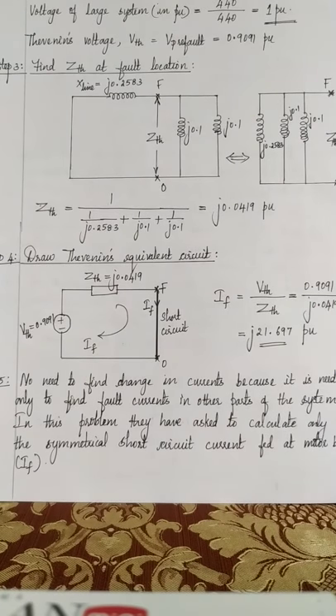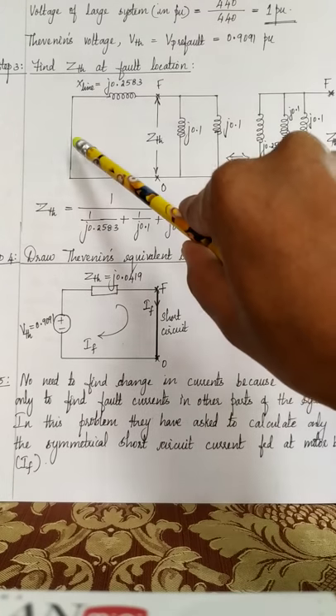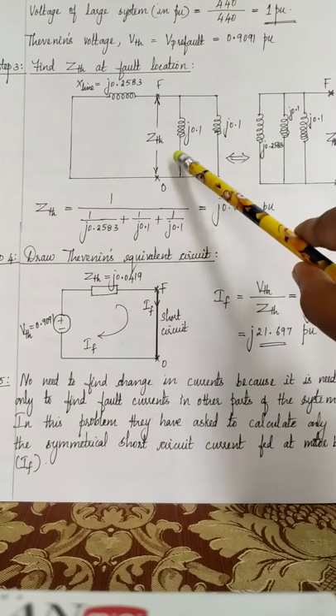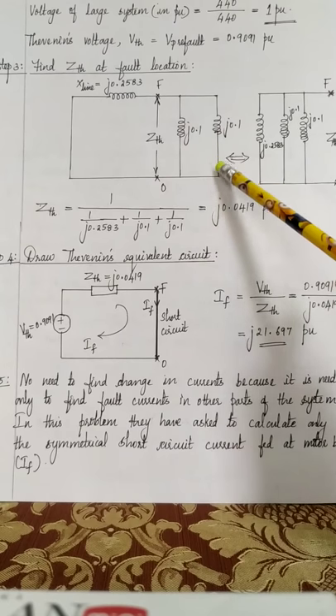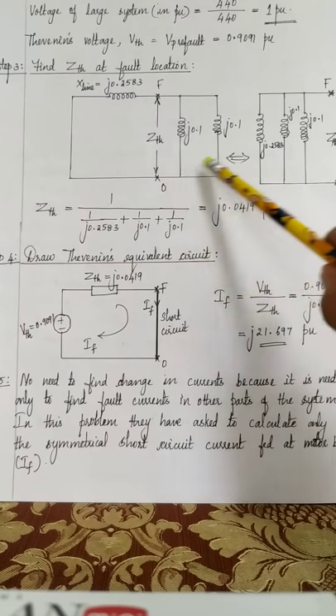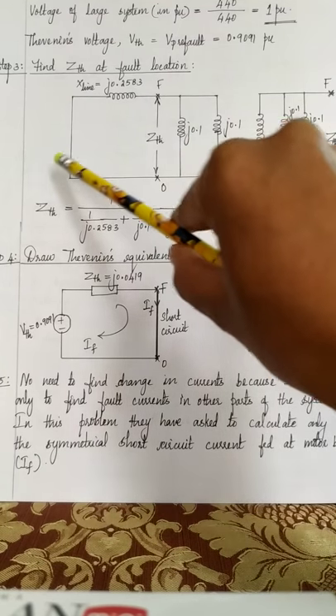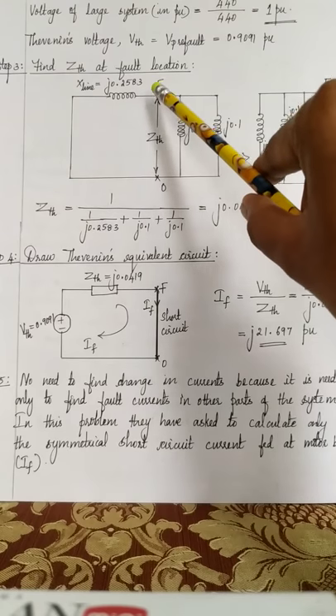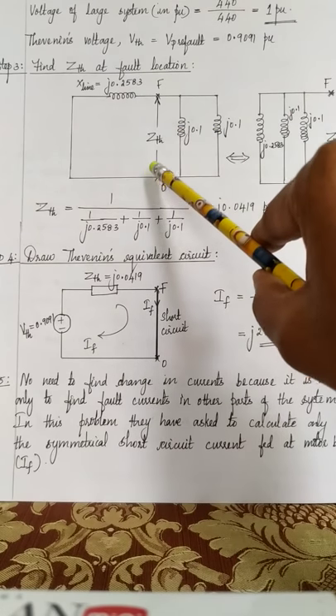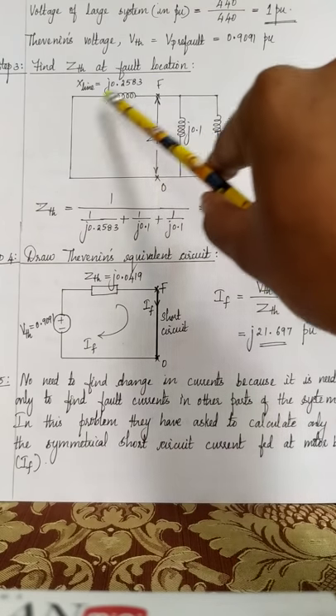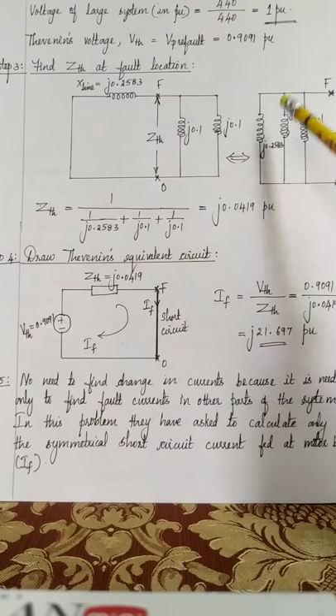you have to find Thevenin's impedance at the fault location. So for that, I am going to short circuit all the voltage sources. So what are the voltage sources? VLS is short circuited, EM1 dash and EM2 dash are short circuited. The motor voltages as well as the large system voltage source are also shorted. So now you represent the ZTH at the fault terminals. So this circuit can be redrawn like this.